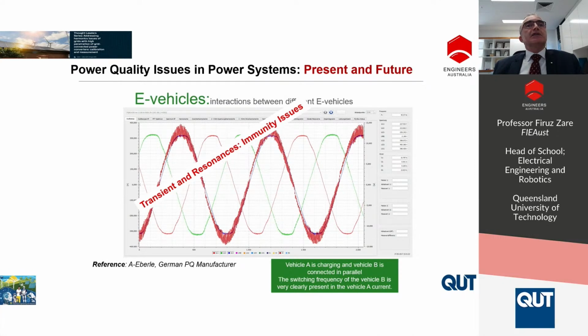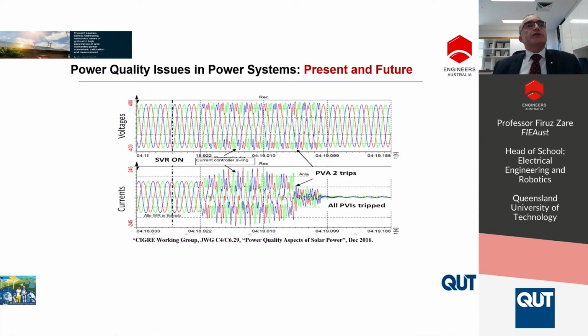So here we see the transient and resonances, which is more or less an immunity issue, and sometimes harmonics can be propagated to the distribution network depending on the frequency and amplitude. This is one of the reports by CIGRE, and again I want to emphasize that here we are talking about 10-12 cycles in which the grid-connected inverter has been affected and then switched off. So when you're talking about high-frequency resonances or harmonics, we are not talking about the conventional harmonic analysis that we can measure, for example, for a day, where the performance is more or less the same. No, you can see that the solar inverter works very well, but within 10 cycles, less than 1 second, suddenly some resonances can happen and the system can basically be affected. So again, this is transient and short-term resonances which are happening and tripping the solar inverter.